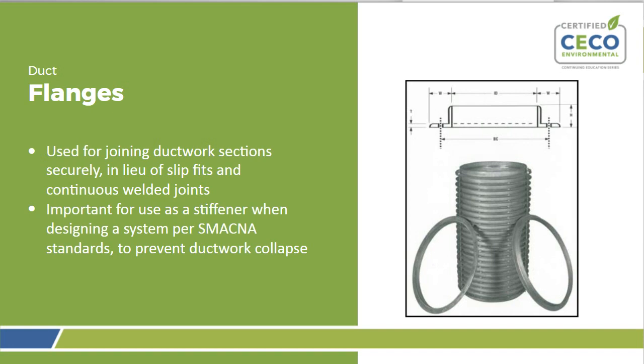SMACNA, Sheet Metal and Air Conditioning Contractors Association, they publish a book for round and rectangular duct, and you can go to the chart. It's based upon the diameter of the duct and the static pressure in the duct, as well as what class is the dust, with class 1 being a light gauge material or light dust material versus class 4, which could be very abrasive and higher concentrations.